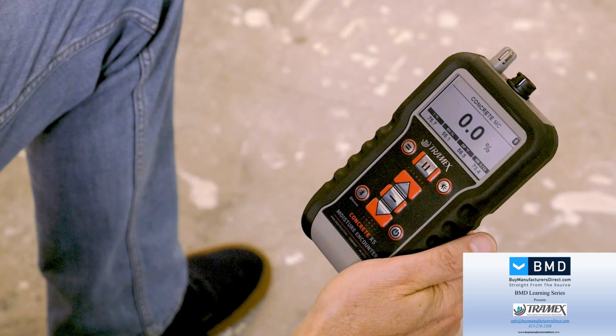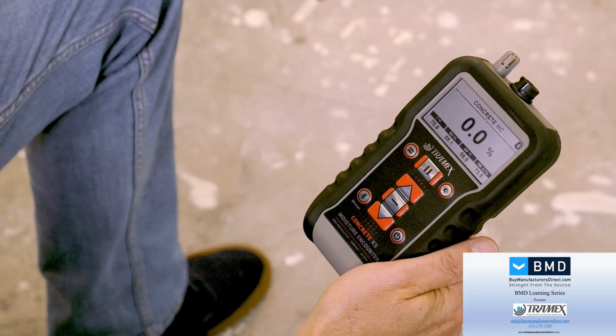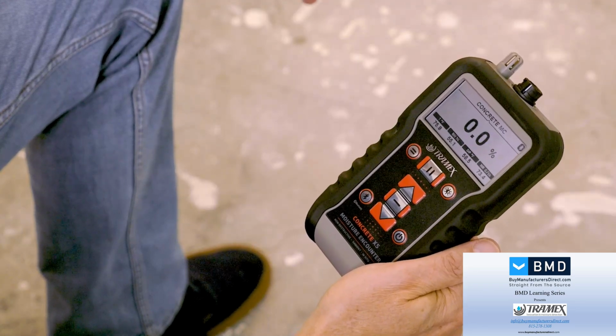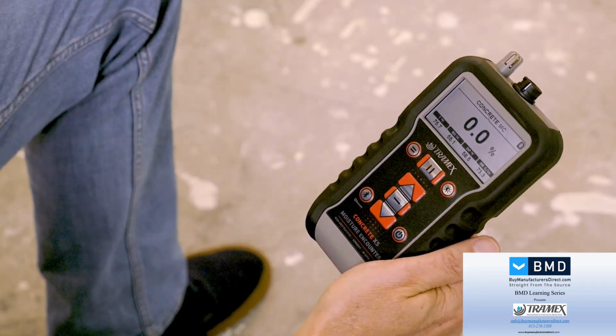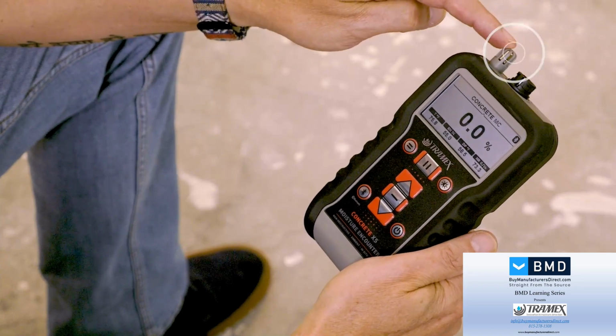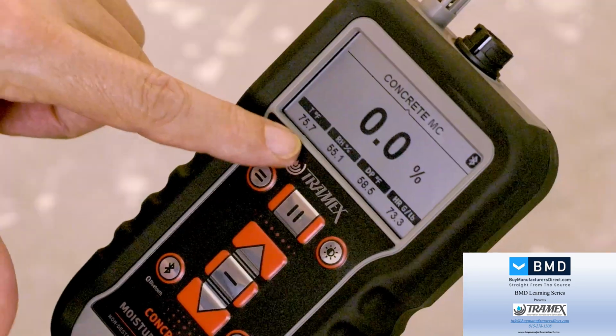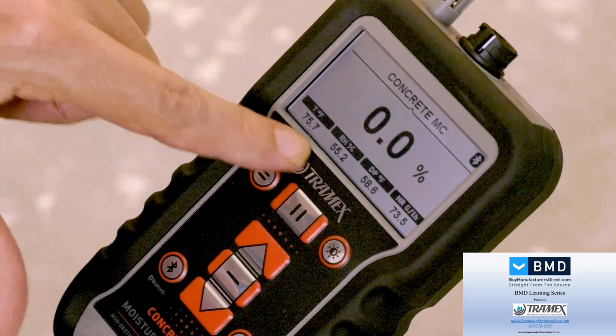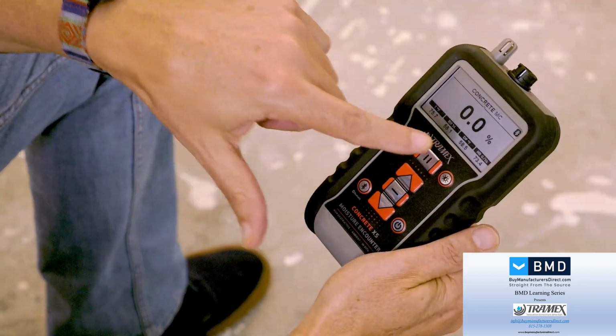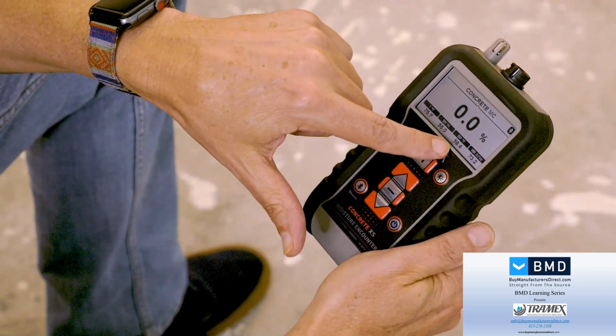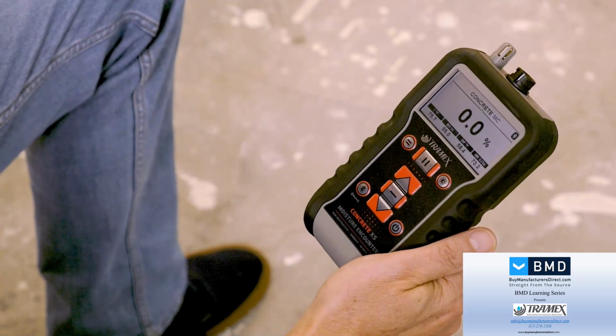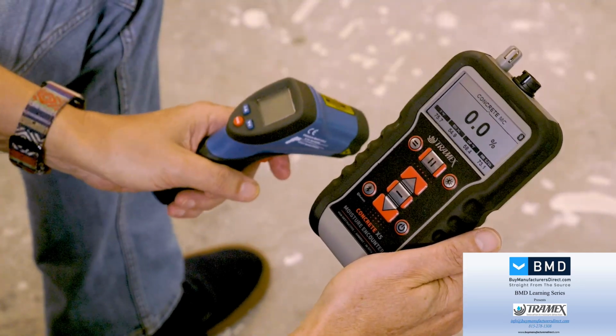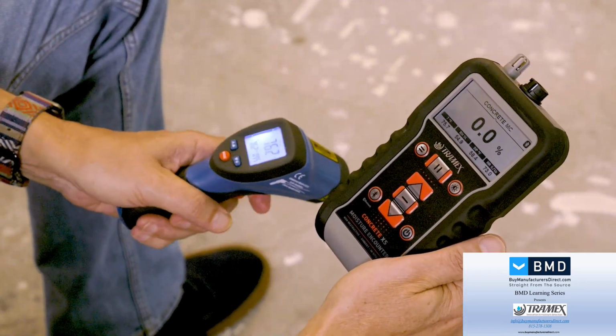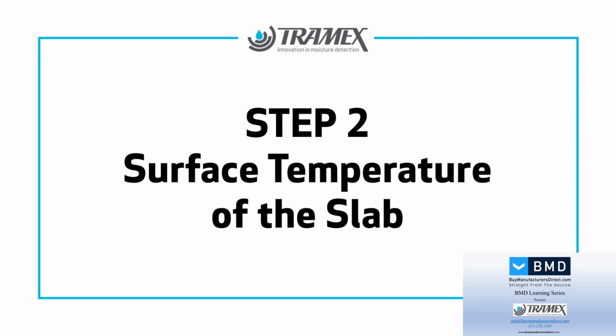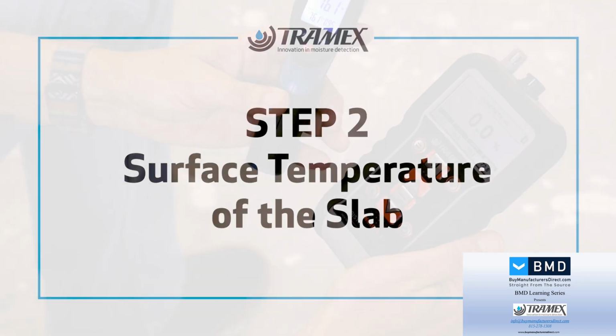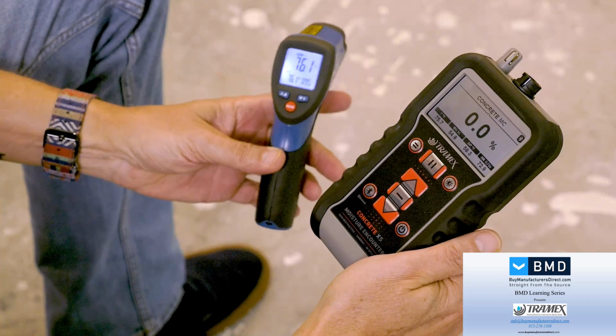So the first data point we're going to collect is the ambient conditions. The nice thing about the CME-X5, it has a built-in hygrometer, which is always listing the ambient conditions across the bottom. And we're going to focus more right now on the dew point. So the dew point is 58 in the air here for the ambient conditions. And then we're going to scan the surface temperature of the slab, and we're at 76.